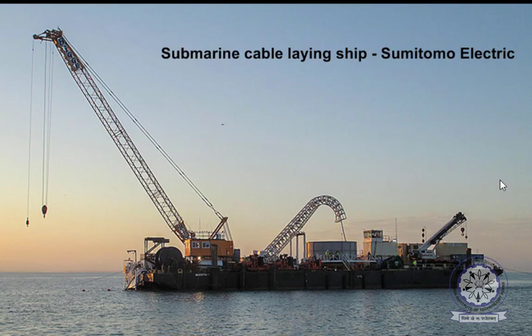In cable insulation, you have seen just now oil impregnated cable insulation and oil filled cable insulation. These two use paper actually, and this is old technology. The paper technology is very old and established. But the problem here is that the paper has to be wound on a conductor. The construction is a tedious process, and once breakdown occurs, joining it is not that easy, because you have to remove the paper carefully, cut it and then connect it. Oil may spill over. So these issues are there as far as repair of conventional HVDC insulation using paper is concerned.